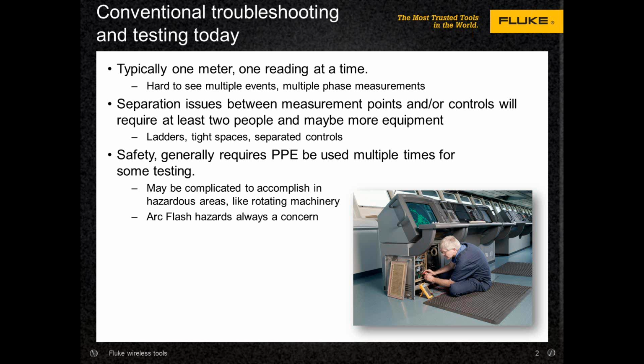One other thing that I've heard in the past is if you use that spool of wire, let's say, if it's a low voltage or a low resistance reading, for instance, you're introducing capacitance and resistance through those leads, aren't you? Right. Wire has a certain resistance or ohms per foot, so you want to be cognizant about how long that cable is and the measurements you're making. So as far as voltage or current goes, it's not a problem, but if you're talking about low-level resistance measurements, it does have an impact.